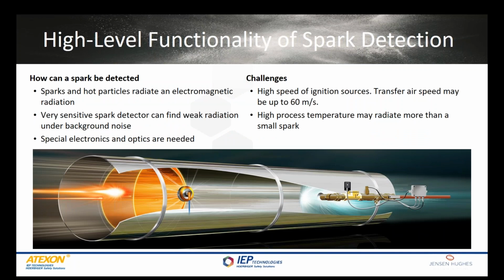It is a common question, how can a spark be detected? Sparks and hot particles, like embers, radiate electromagnetic radiation. Spark detector is very sensitive to this radiation, even through some dust layers. Very special electronics and optics are needed because sensitivity level and response time have to be at so high a level. There are also challenges like very high material flow speed or high process temperature, which can radiate many times stronger signal than a small spark. Spark detectors are sensitive to a wide range of radiation from visible light to infrared range.